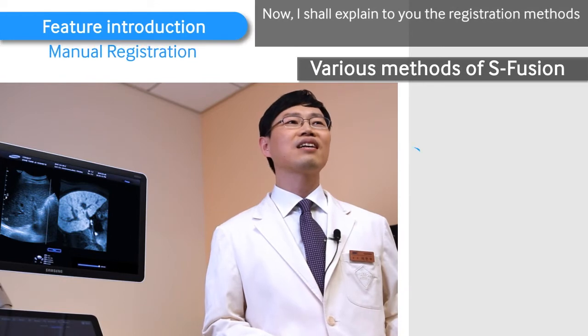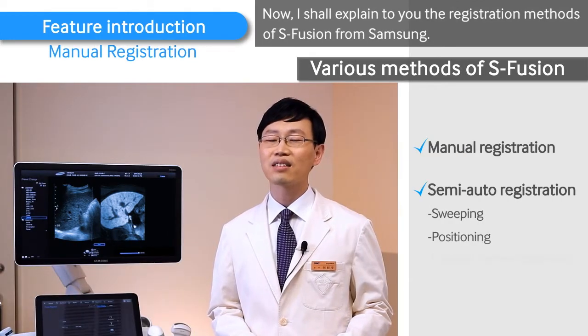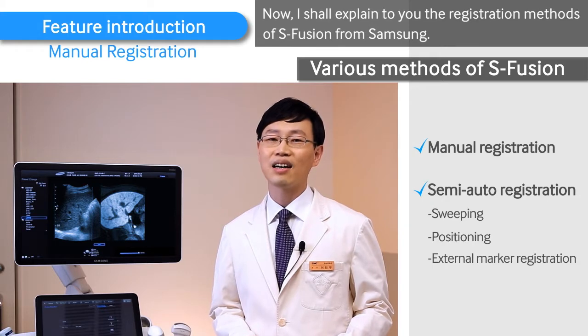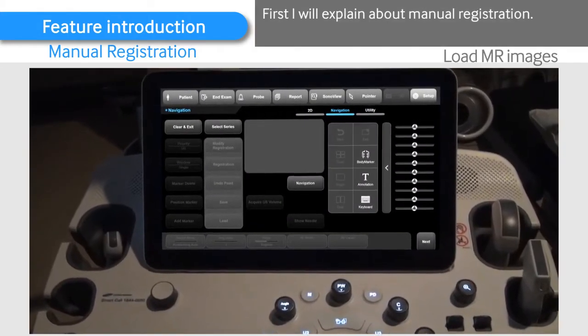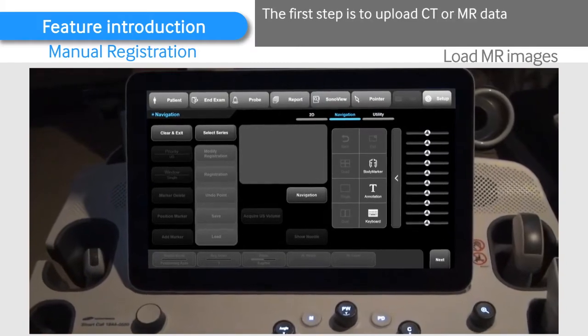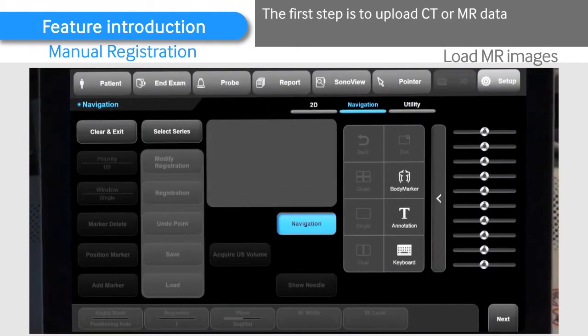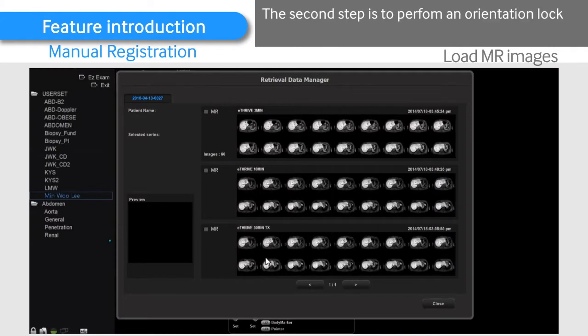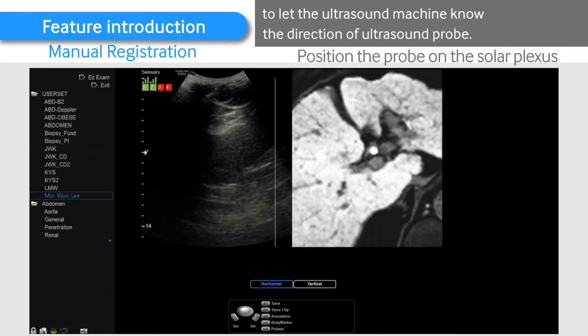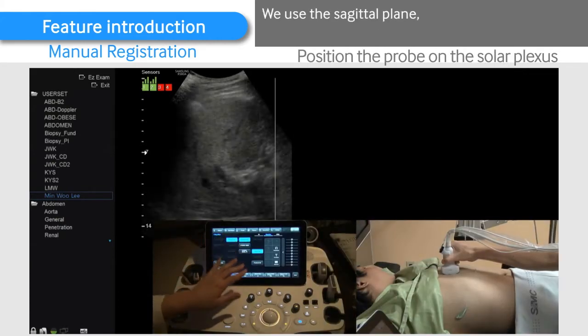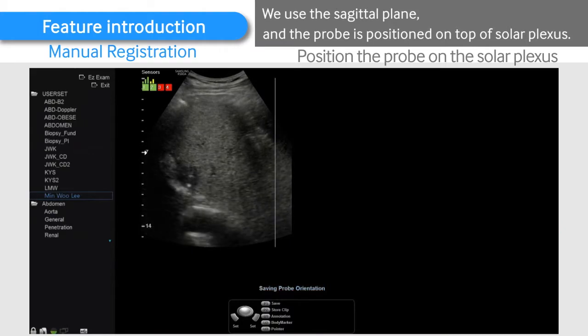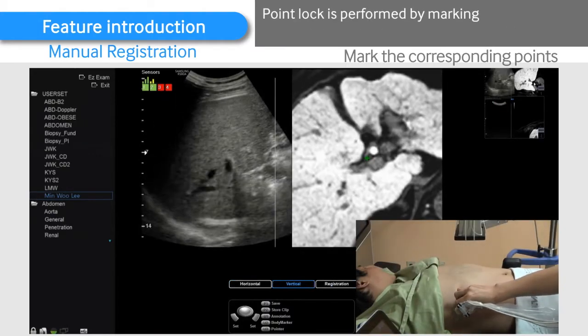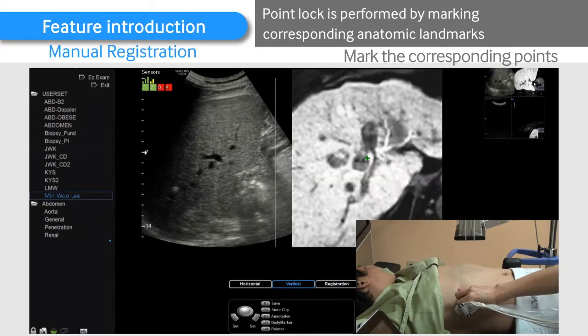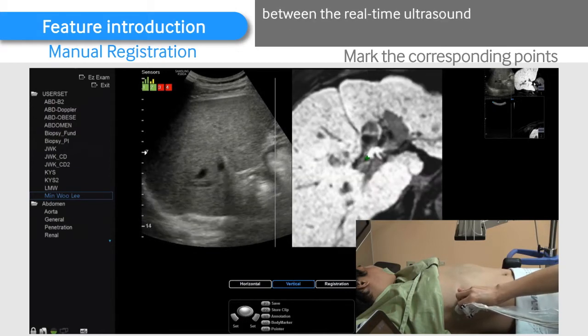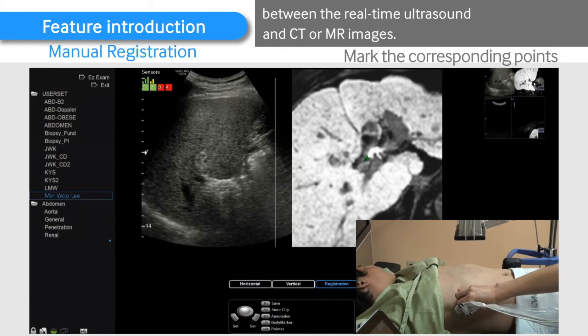Now, I shall explain to you the registration methods of S-Fusion from Samsung. First, I will explain manual registration. The first step is to upload CT or MR data to the ultrasound machine. The second step is to perform an orientation lock to let the ultrasound machine know the direction of the ultrasound probe. We use the sagittal plane, and the probe is positioned on top of the solar plexus. The point lock is performed by marking corresponding anatomic landmarks between the real-time ultrasound and CT or MR images.